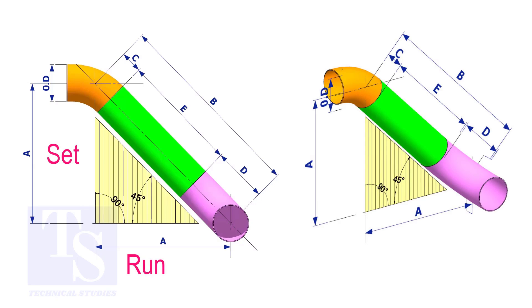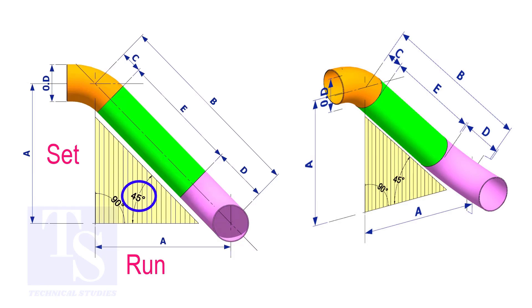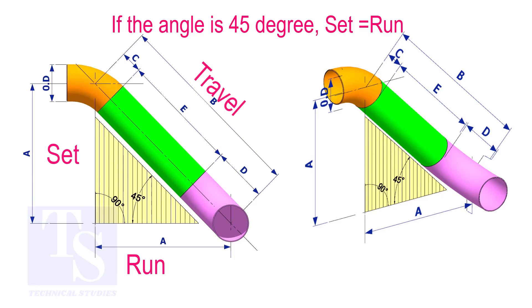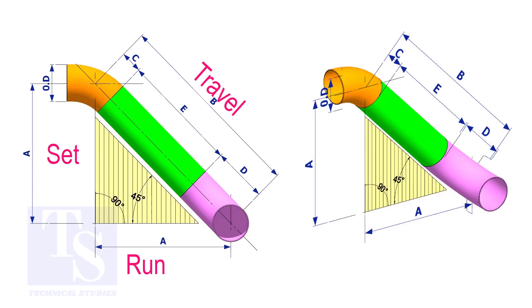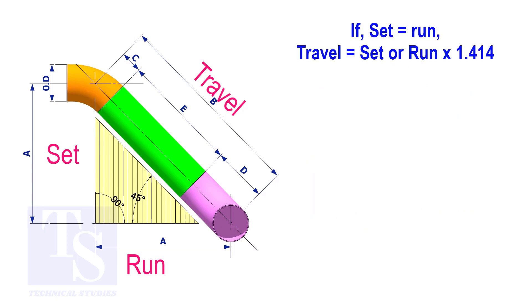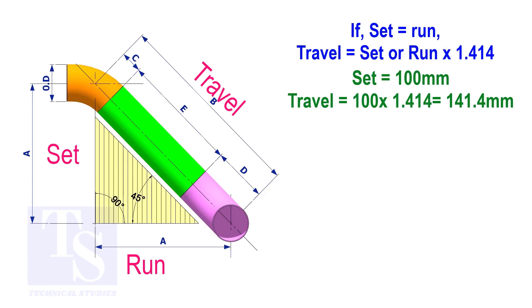In an offset, if the included angle is 45 degrees, the set and the run shall be the same. If the value of the set and the run are equal, the value of the travel is the set or the run multiplied by 1.414. Assume that the value of the set is 100. The value of the travel is 100 multiplied by 1.414, which equals 141.4.